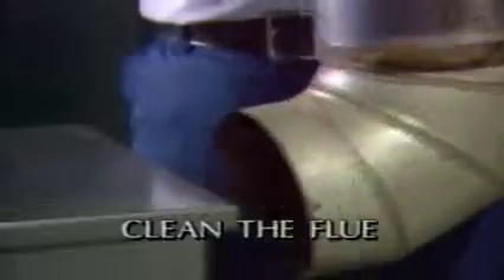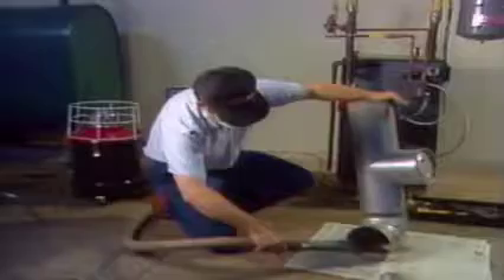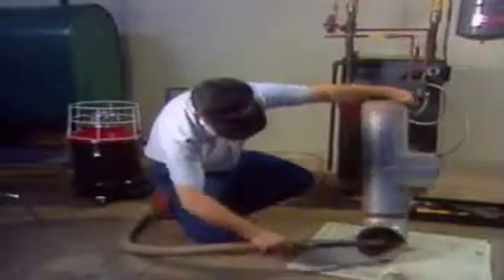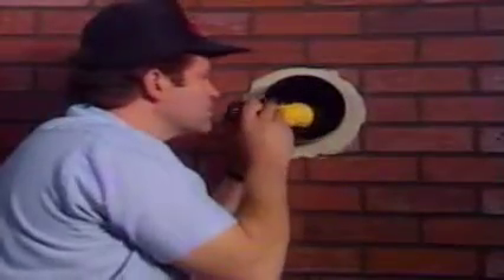Then turn off the power to the appliance and the oil valve at the burner. Next, remove the flue pipe at the breech and the chimney. Clean it, making sure you follow good housekeeping procedures. Then inspect the chimney for any blockage, brick or mortar damage, or moisture damage. Remove any obstructions and report any needed repairs on your service log.